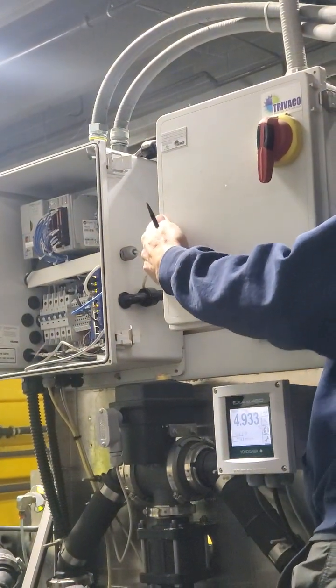If I clear that, see, I can see the 3 lights come on. It's just another way of visually checking stuff. I've never seen one of these relays go bad, but if it doesn't reset, you probably have a tripped overload or a blown fuse, something in that box. That tells me, yeah, there's probably something going on in here. So what I'd have you check is, hey, do you have 3 lights on your safety relay? Just to know where it's at.